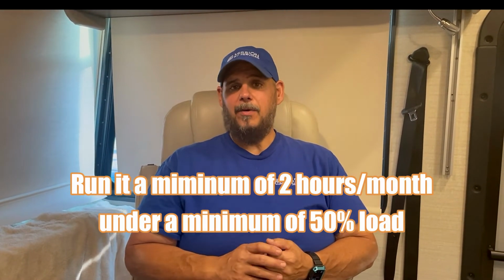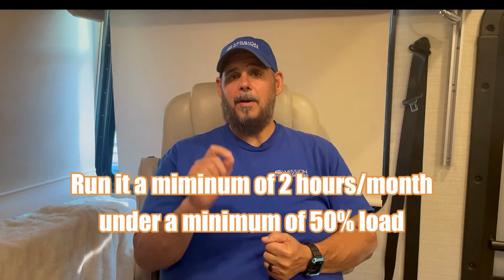Another thing that you should be doing to keep your generator in tip-top shape is you should be running that generator a minimum of 2 hours every month under a minimum of a 50% load. The reason we're doing this is we're making sure that the magneto in there that creates that power for you to run an AC unit or your microwave or your other power or charge your batteries is running in peak perfection. It's keeping your brushes doing what they're supposed to do, and your slip rings are staying clean. That generator needs to run under load. You want to put that generator under stress, run it through its paces for a couple hours a month.